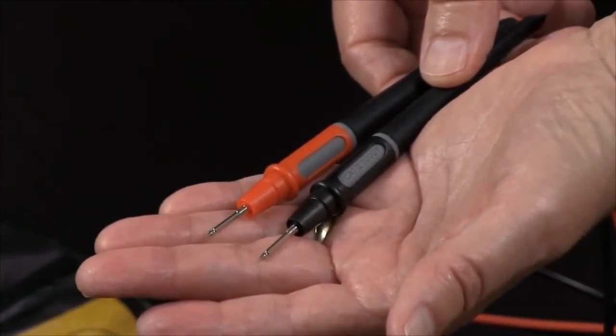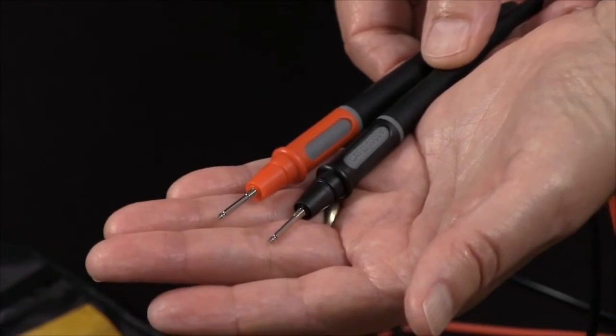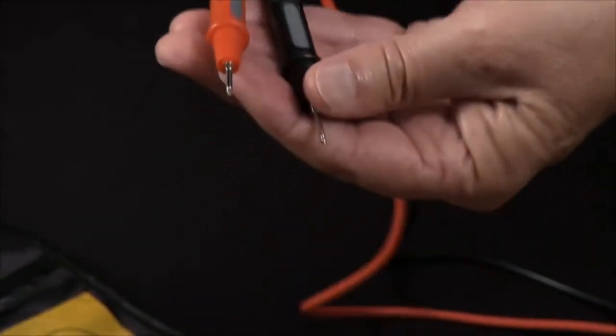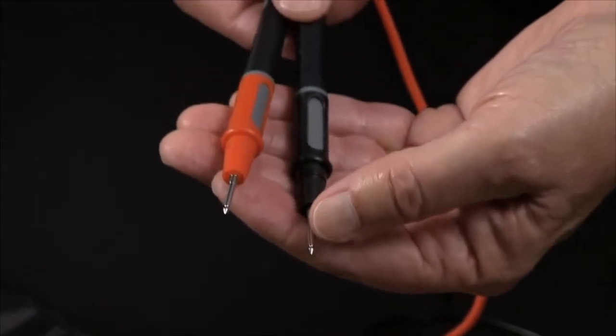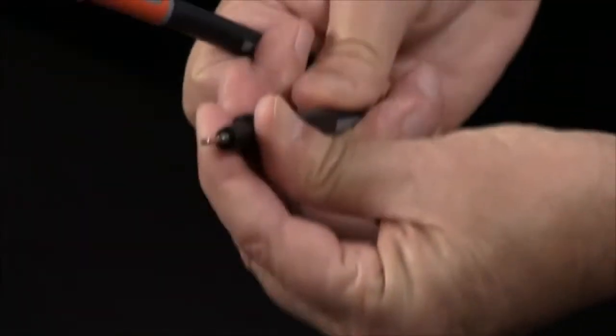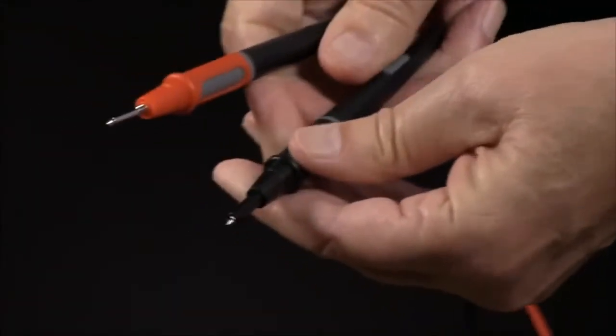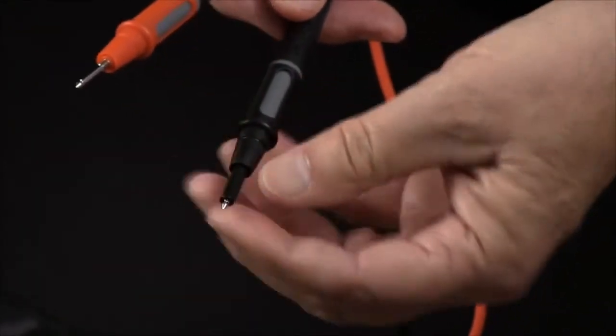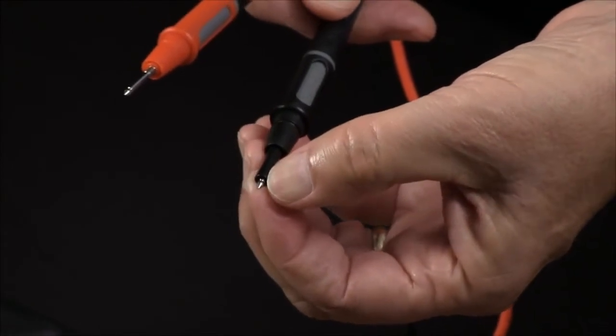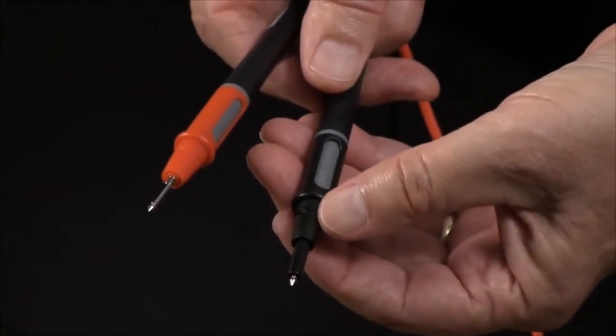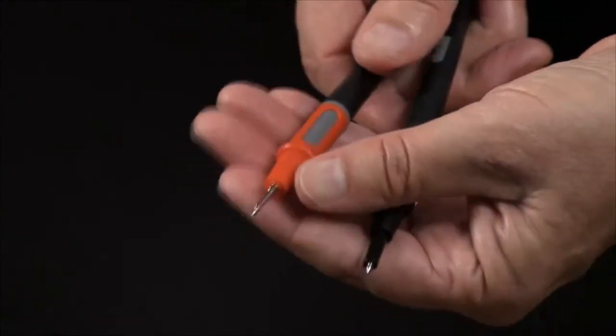But when you get into a high-energy electrical situation, you need something with less exposed metal. In this configuration, these probes are rated Category 2, 1000 volts. But they have a twist cover capability, and when you reduce the amount of exposed probe tip, the category rating goes to Category 3, 1000 volts, and Category 4, 600 volts.